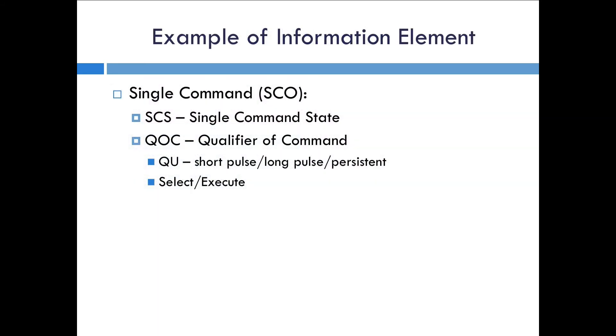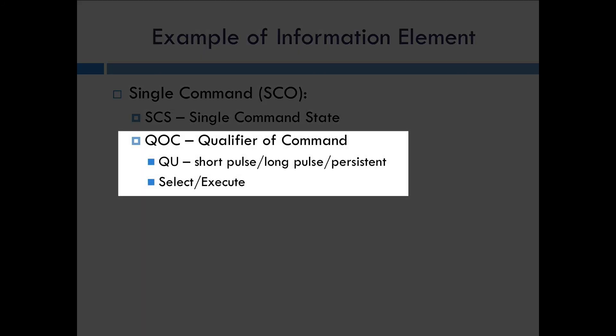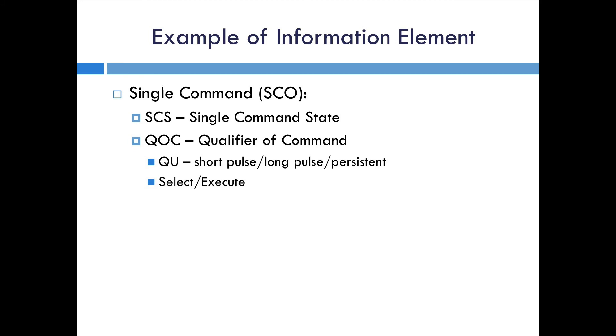Here's another example, this time for a command. A single command tells you the command state and then the qualifier for the command. The qualifier includes the operation: similar to DNP3 modes like latch on, in IEC 60870-5 you have short pulse, long pulse, or persistent. Persistent sets the output and it remains until changed by another command, whereas short and long pulses pulse the output for a predefined period of time. Unlike DNP3 where you can specify the pulse length in the command itself, in IEC 60870-5 the pulse length is a configuration option and you simply specify short pulse or long pulse. The qualifier also indicates whether this is the select or execute for the command.